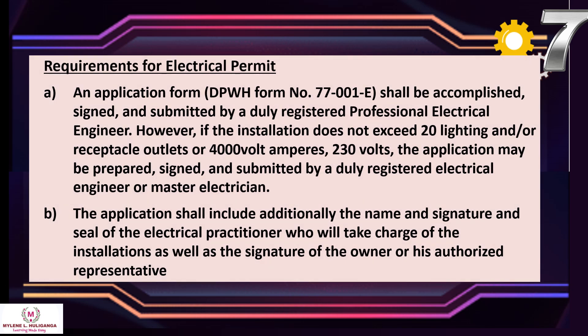Requirements for an electrical permit: (a) An application form (DPWH Form No. 77-001E) shall be accomplished, signed, and submitted by a duly registered Professional Electrical Engineer. However, if the installation does not exceed 20 lighting and/or receptacle outlets or 4,000 volt-amperes at 230 volts, the application may be prepared, signed, and submitted by a duly registered Electrical Engineer or Master Electrician. (b) The application shall additionally include the name, signature, and seal of the electrical practitioner who will take charge of the installations, as well as the signature of the owner or authorized representative.